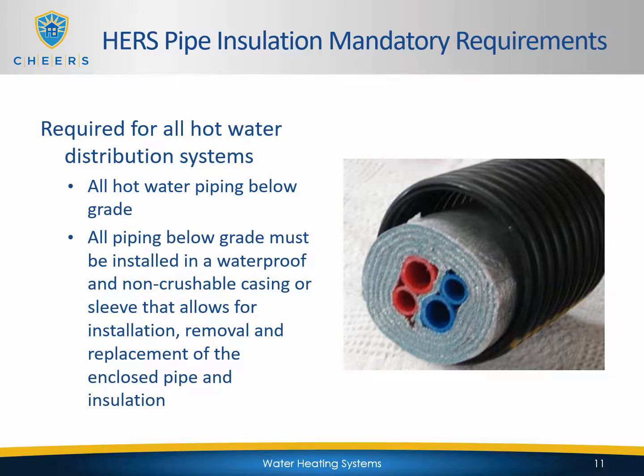Also, all piping below grade must be installed in a waterproof and non-crushable casing or sleeve that allows for installation, removal, and replacement of the enclosed pipe and insulation. Piping below grade that serves any islands, sinks, or other island fixtures or appliances may be insulated with 1/2 inch wall thickness insulation.